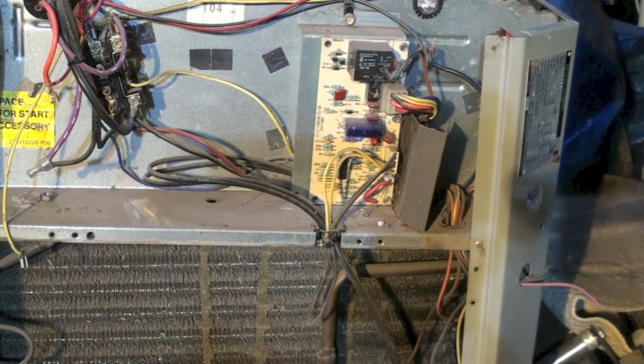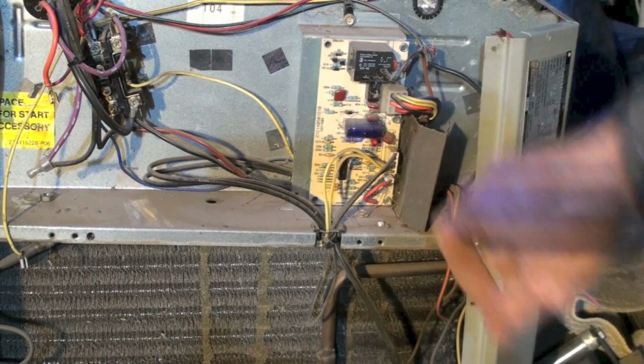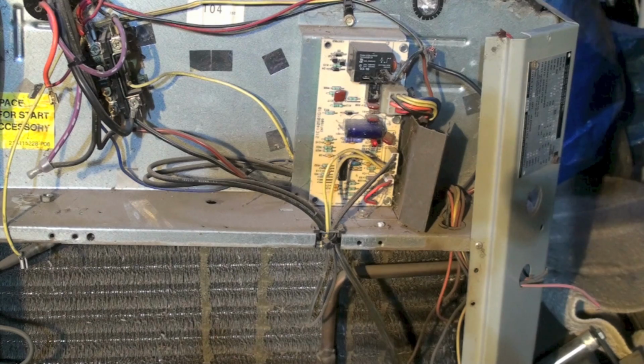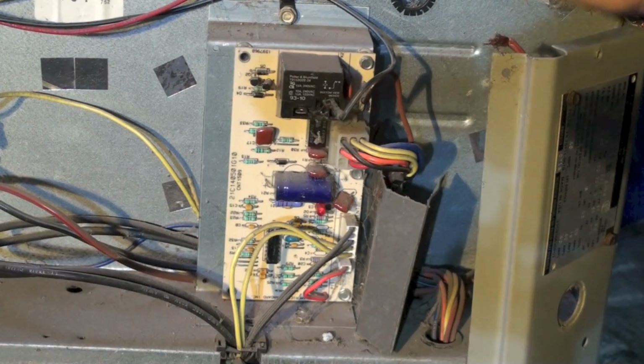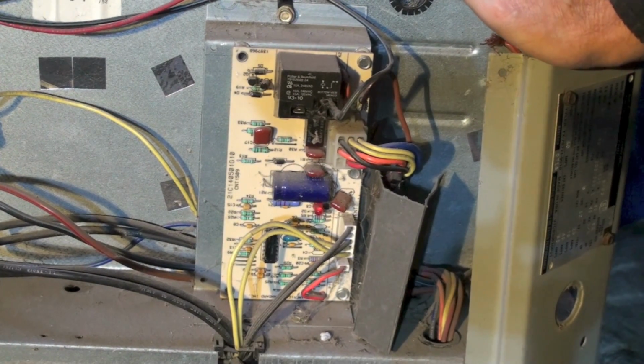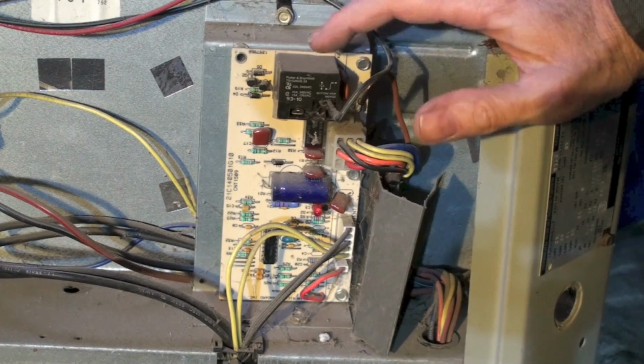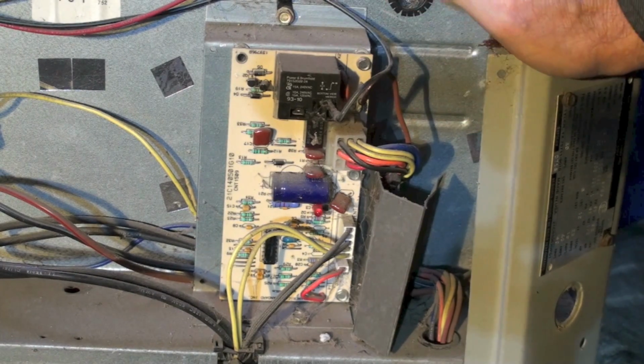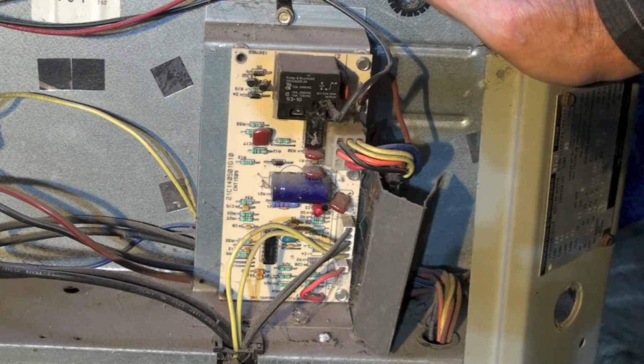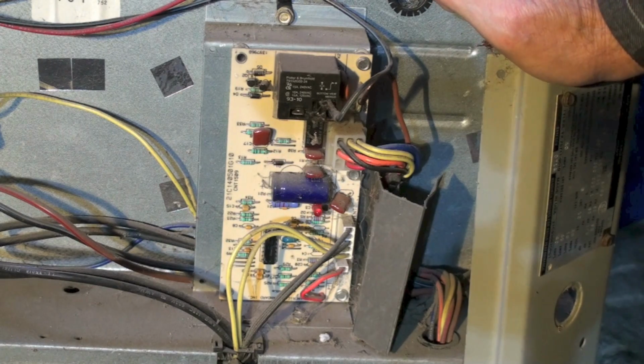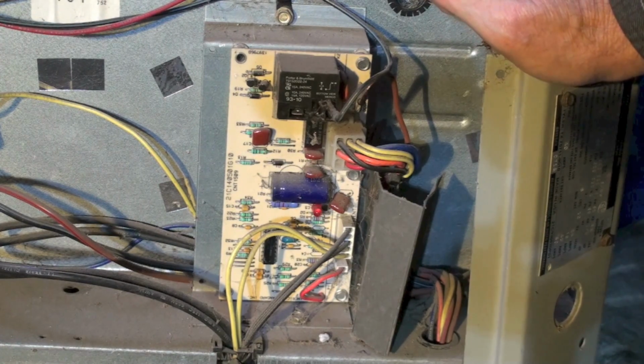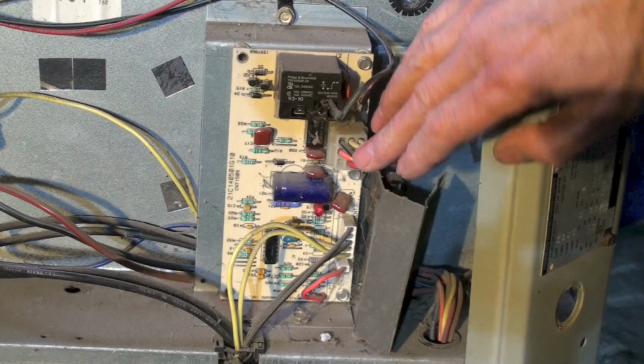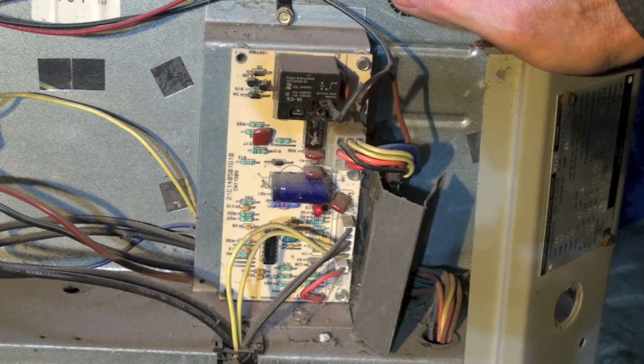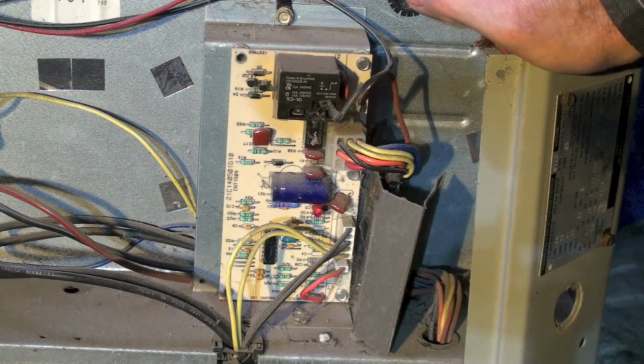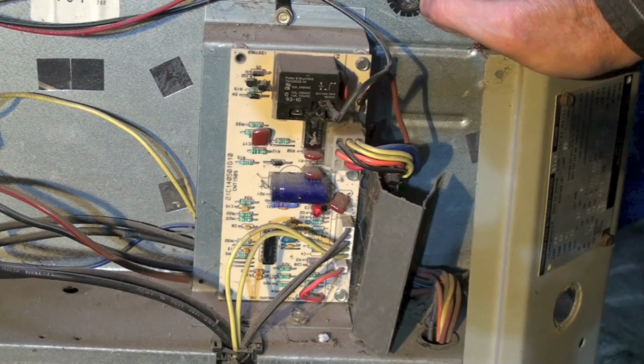Okay, here we're showing an example of a demand defrost right there. Let me get a little closer to it. Okay, this one has all the things that any defrost would have. There's a relay right here that's going to shut off the outdoor fan when it goes into defrost. And this plug here goes to the reversing valve and several other parts, so it can shift the reversing valve.